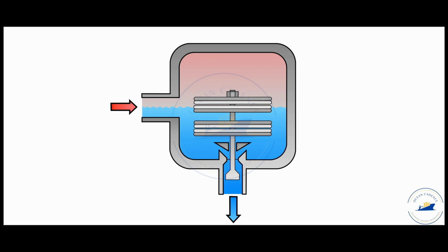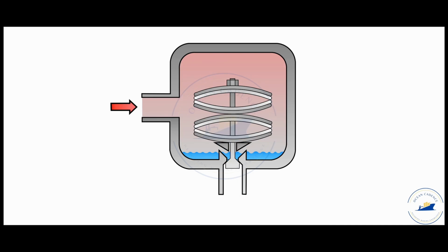Thereby again, when the condensate level is not enough and the steam is filling the majority part of the chamber, the bellows would expand again and retain the original shape, and thereby close the trap condensate drain side or the return line. Now what this does is that it reduces the number of interlinked moving parts. That is, the entire procedure is dependent upon the expansion coefficient and the differential of the bellow and its material nature. So it gets rid of the moving part.